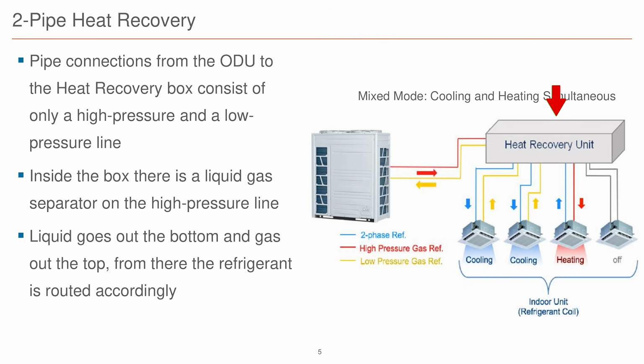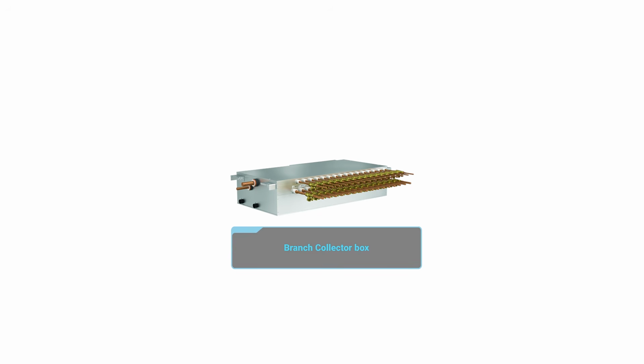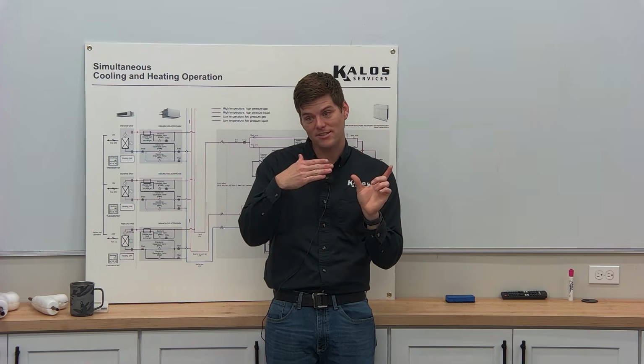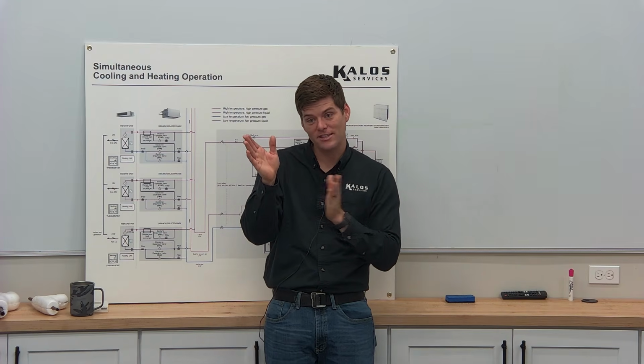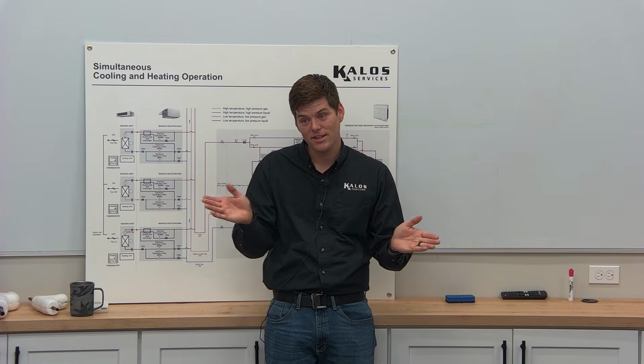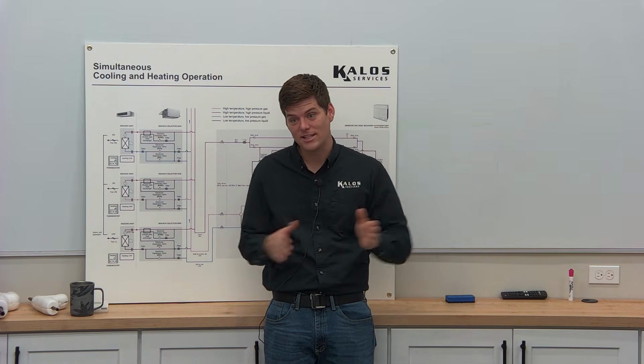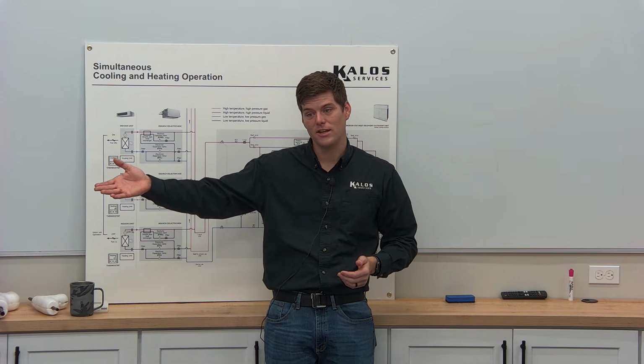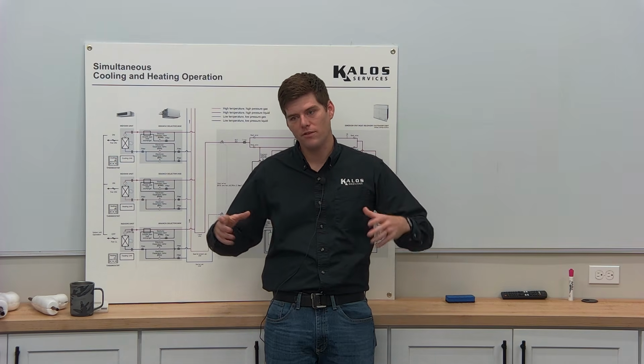So as you can see here, what happens is the heat recovery box itself is the one that is actually generating the liquid needed for indoor units. There's a refrigerant gas separator inside that they call branch collector boxes or controller boxes, right? BC, everybody calls it something different. In the box, it gets hot gas. It skims hot gas off the top of the line, takes the liquid from the bottom, separates the two, gives the liquid to whatever units are in cooling, takes the hot gas, gives it to the indoor units that are actually calling for heating. And there's a little more that takes place, which we'll dive into in another class.